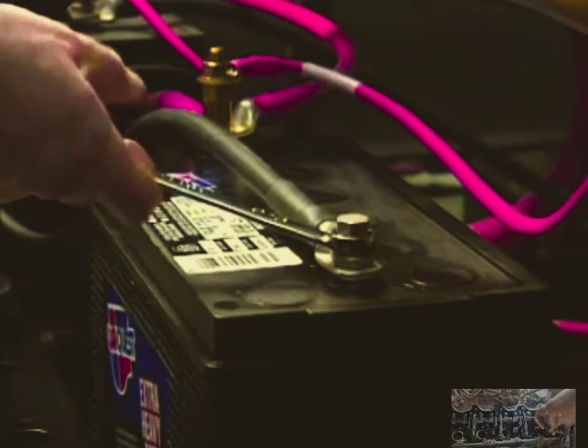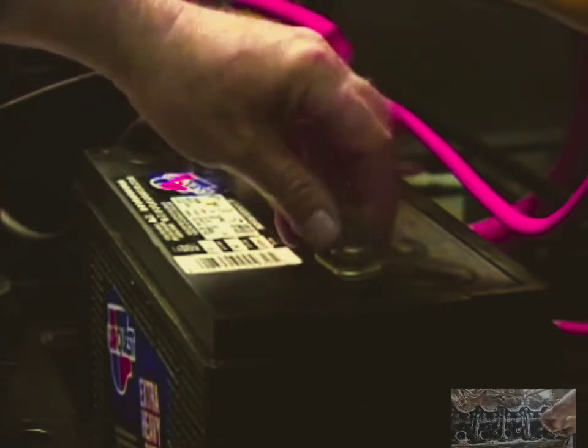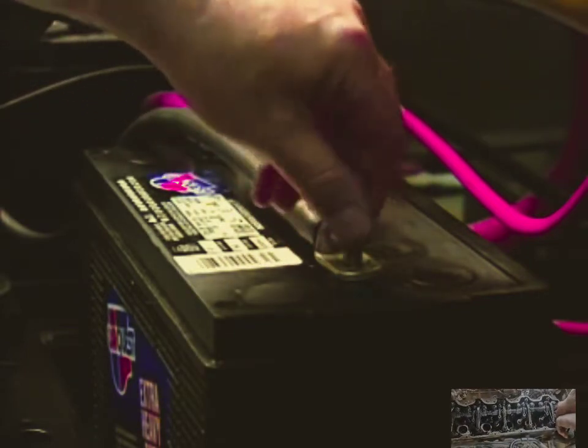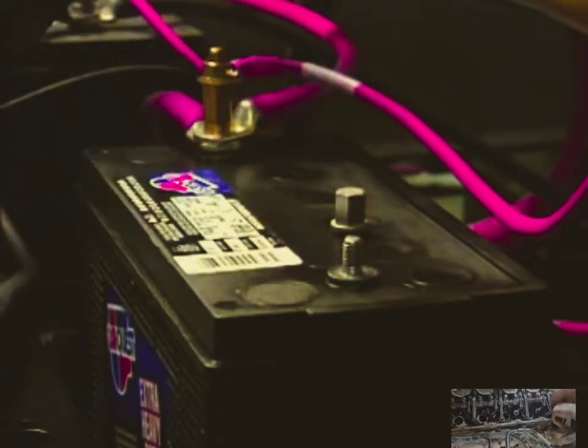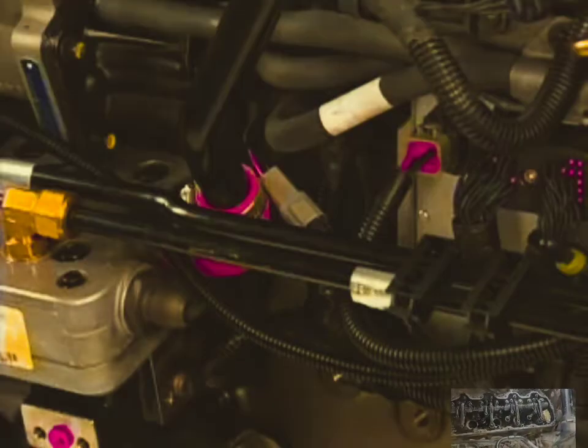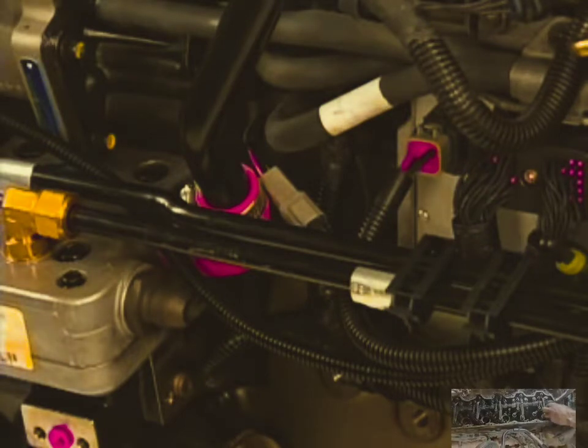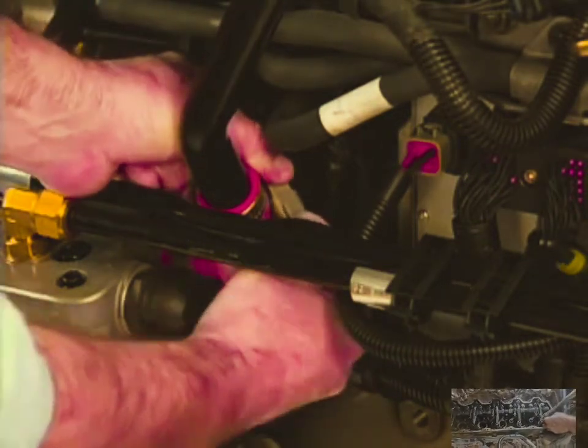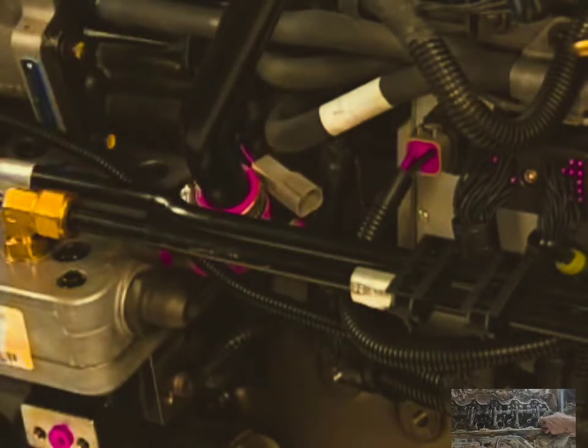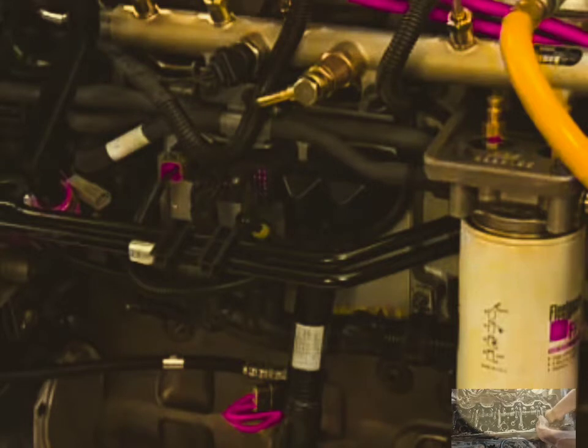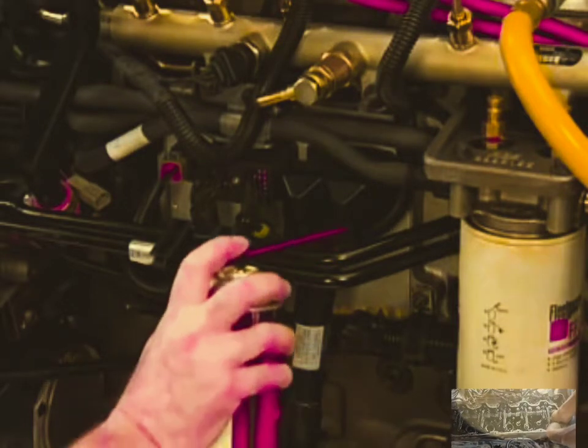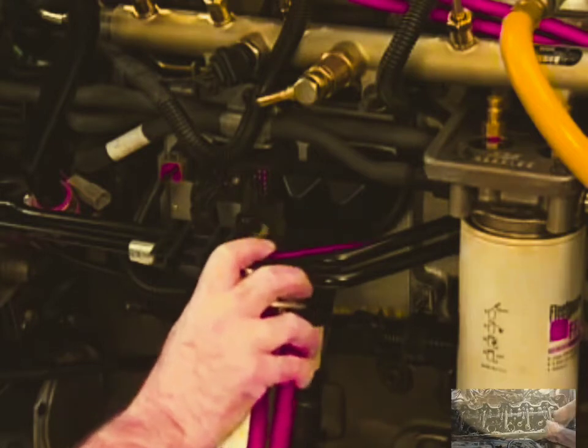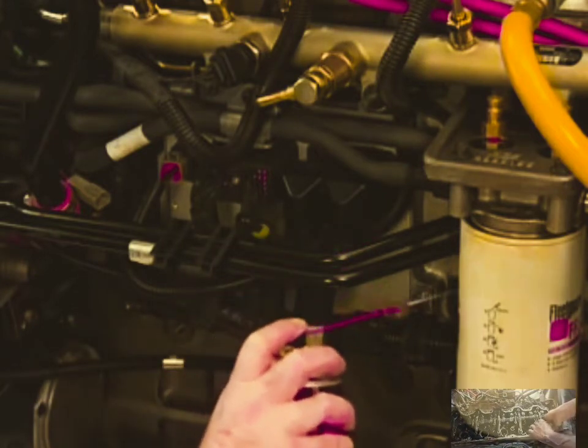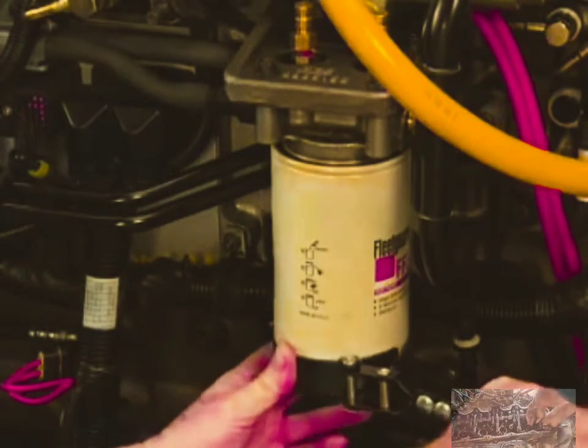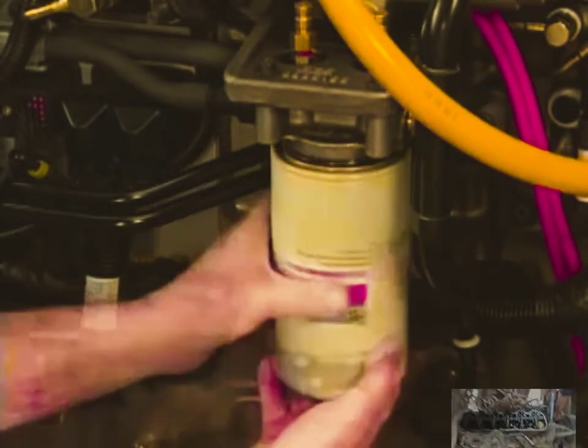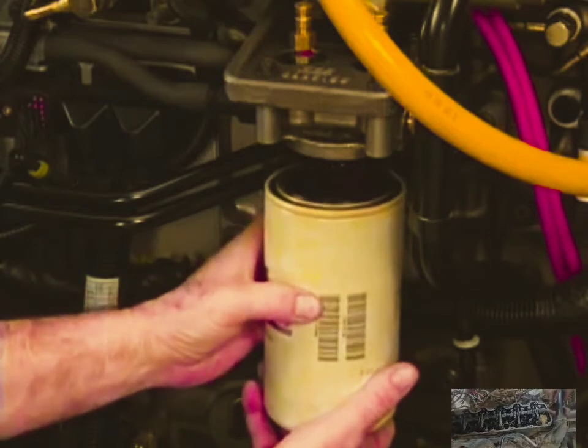Should it be necessary to replace the lift pump, begin by disconnecting the battery. Always disconnect the negative terminal first to reduce the risk of arcing. Disconnect the wiring to the lift pump. Thoroughly clean all fittings and components before disassembly. Debris, water, steam, or cleaning solution that enters the fuel system can cause severe damage. Removal of the pressure side fuel filter provides needed access for service.